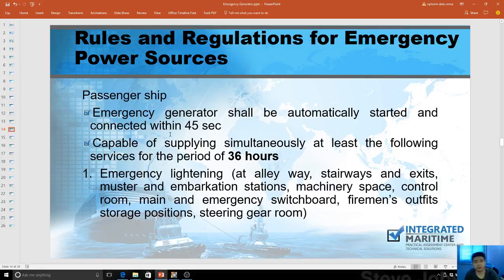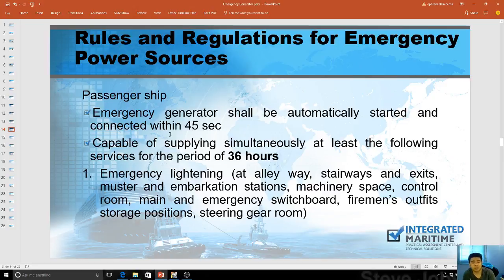On passenger ships, the emergency generator shall be automatically started and connected within 45 seconds. On board, 45 seconds is actually a very long time, especially when maneuvering. There is a specific timer called the cut-in time that can be adjusted. We usually go for 10 to 14 seconds on board. But the regulation maximum is 45 seconds — the faster the generator cuts in, the better the retrieval of power.